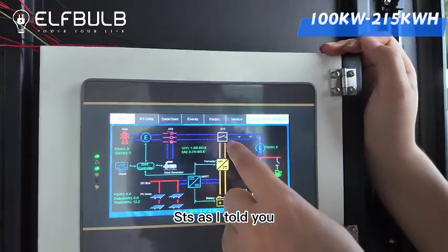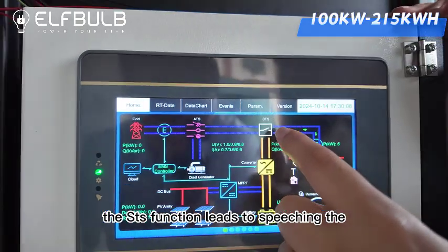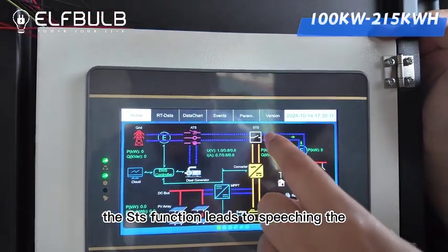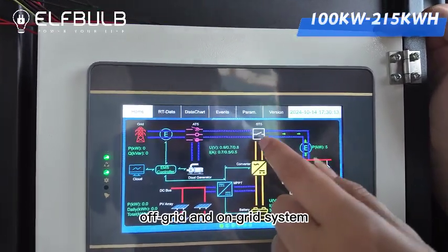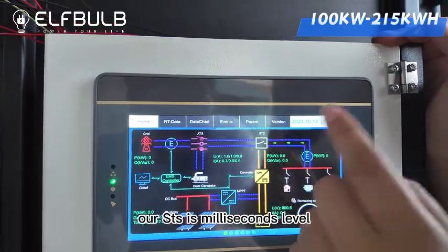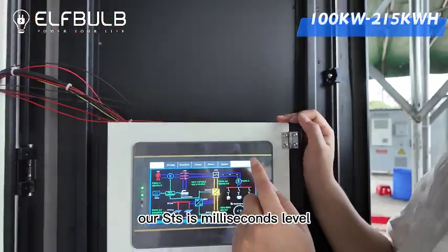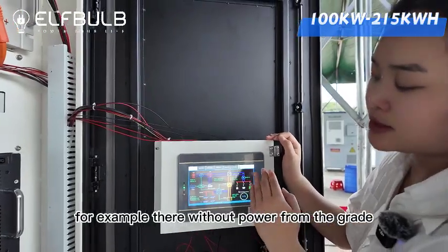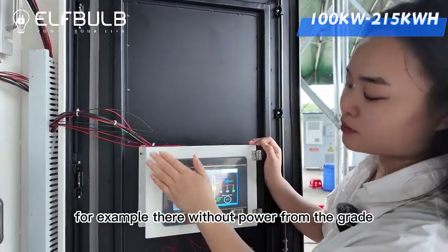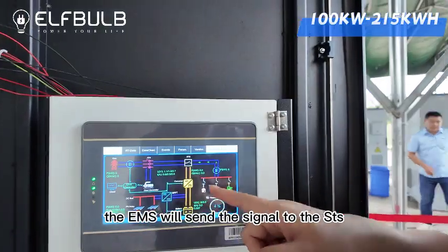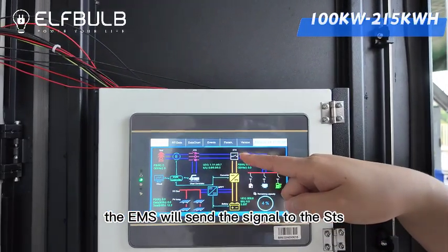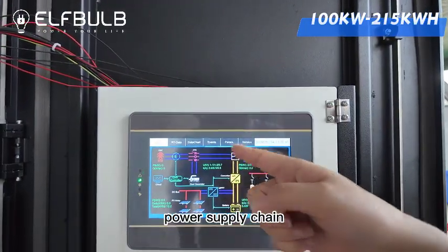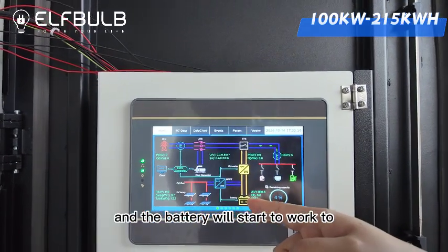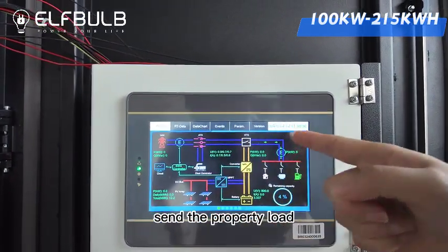As I told you, the function of the STS is to switch between the off-grid and on-grid system. Our STS is millisecond level. For example, if there's no power from the grid, the EMS will send a signal to the STS to cut off the grid power supply chain, and the battery will start to work to send power to the load.